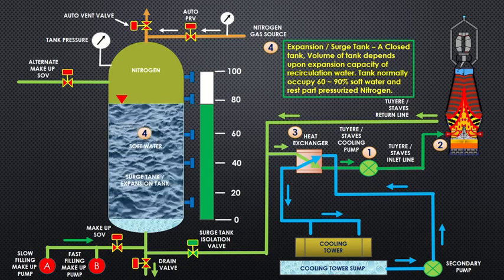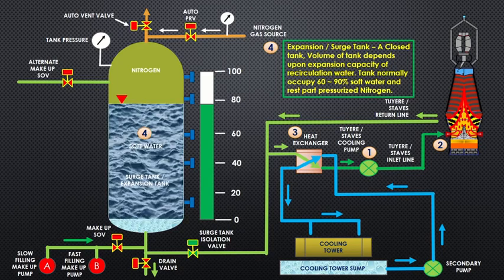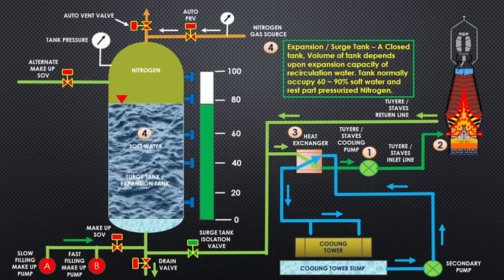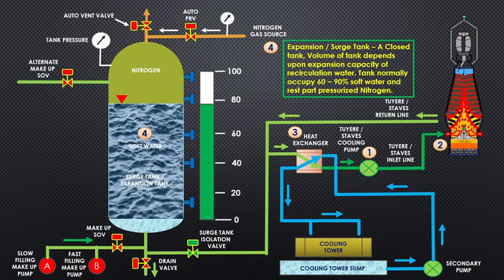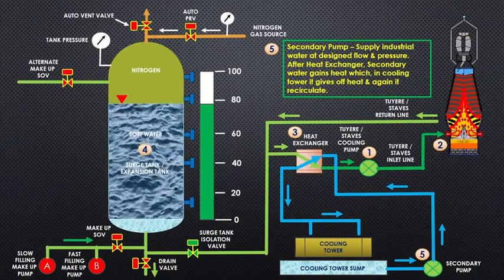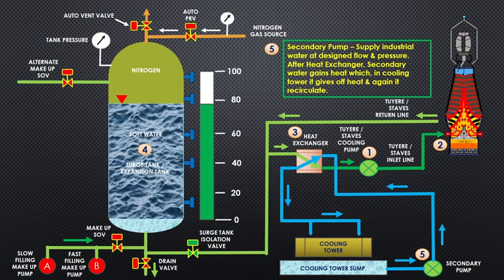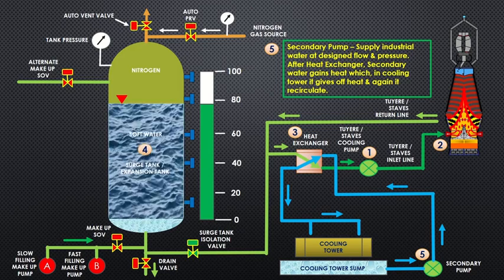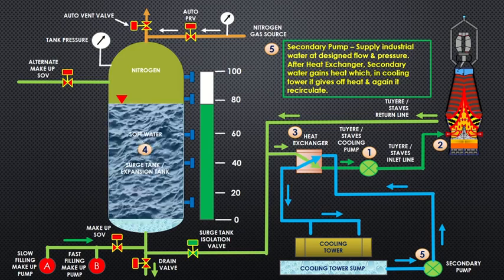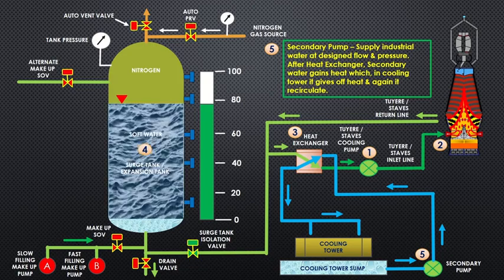Tank normally occupies 60 to 90 percent soft water and the rest part is pressurized nitrogen. Secondary pump supplies industrial water at designed flow and pressure. After heat exchanger, secondary water gains heat which in cooling tower it gives off heat and again it recirculates.